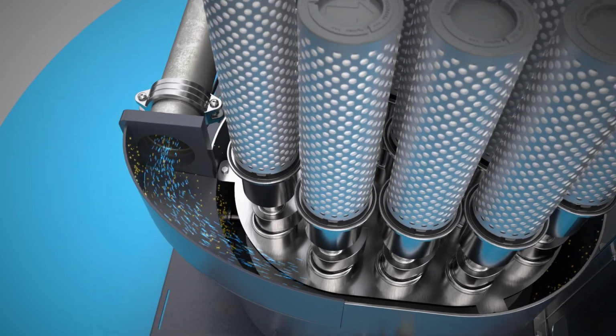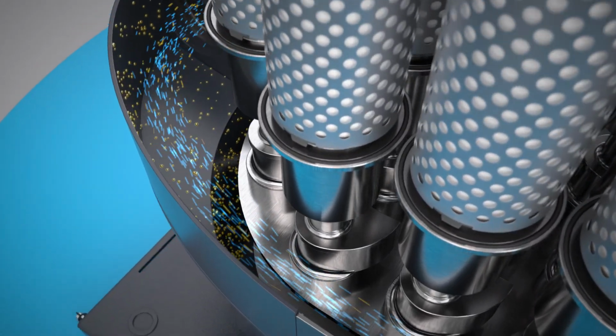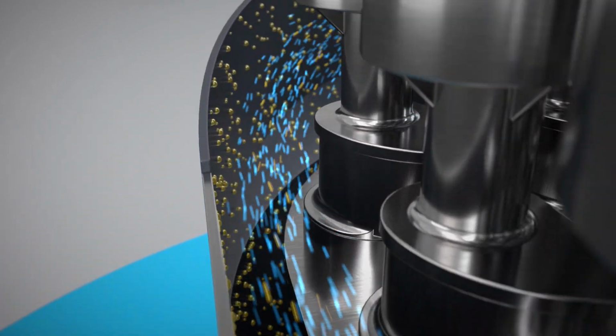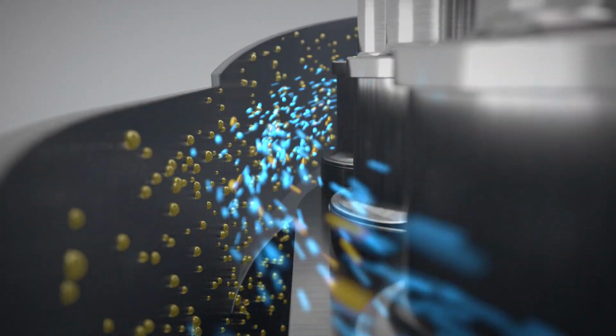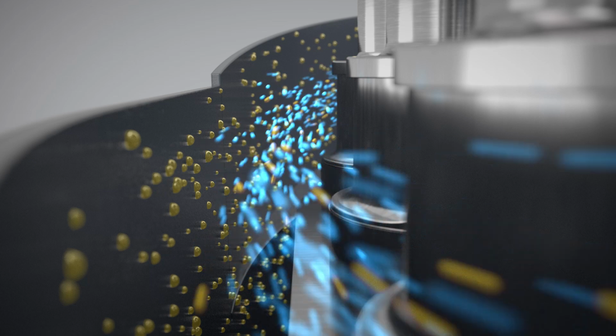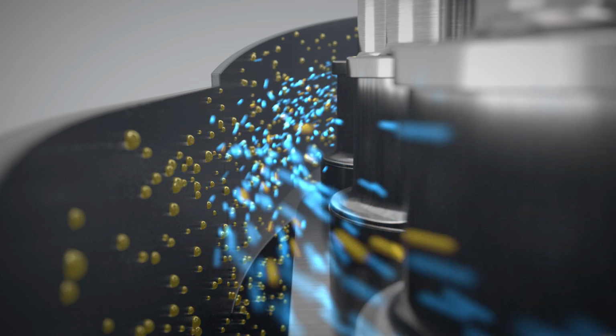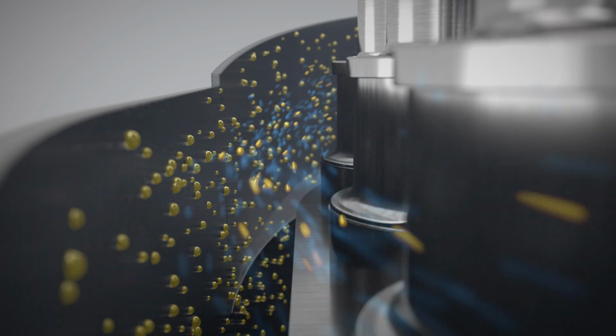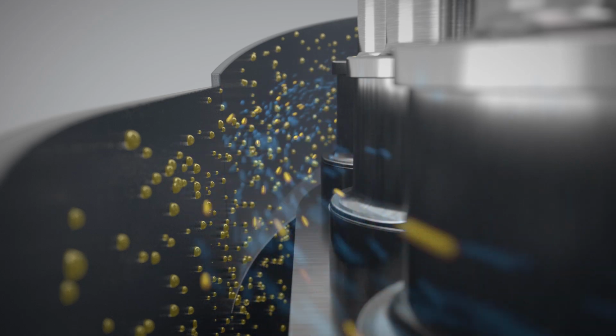The first stage takes care of the heavier oil particles. In this stage, the air and oil mixture enters the vessel at high speed. There are centrifugal forces at work here because of the high speed of the mixture, and this allows for the heavier oil particles to drip down the walls into the oil reservoir.